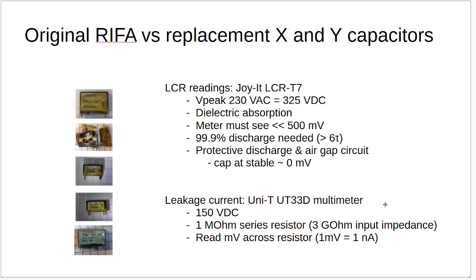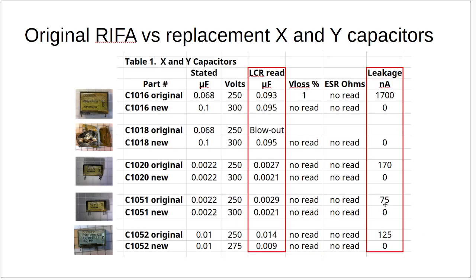Now, these meters have a 3 gigaohm input impedance on the millivolt setting, which means that it's not going to act as a voltage divider. And so with a 1 megaohm resistor, it's pretty linear. So in the millivolt setting, you measure across that 1 megaohm resistor, and 1 millivolt will equal 1 nanoamp. Pretty straightforward. But how do these play out in terms of numbers?